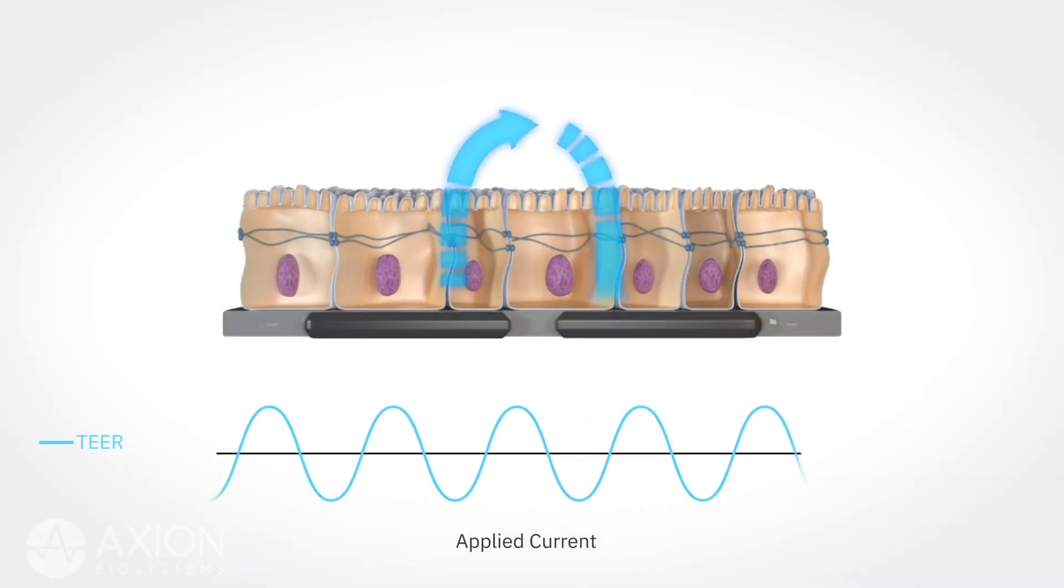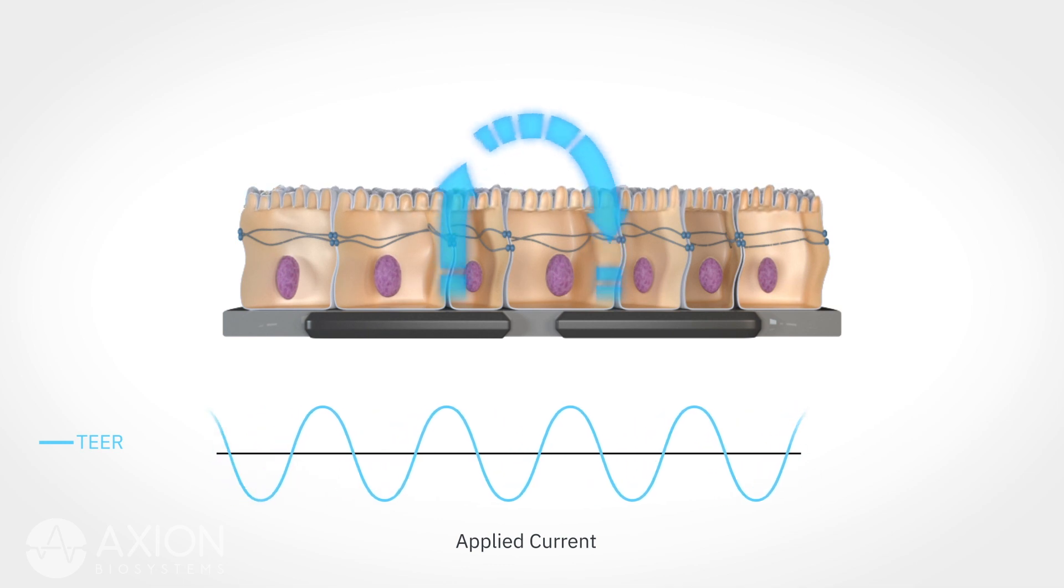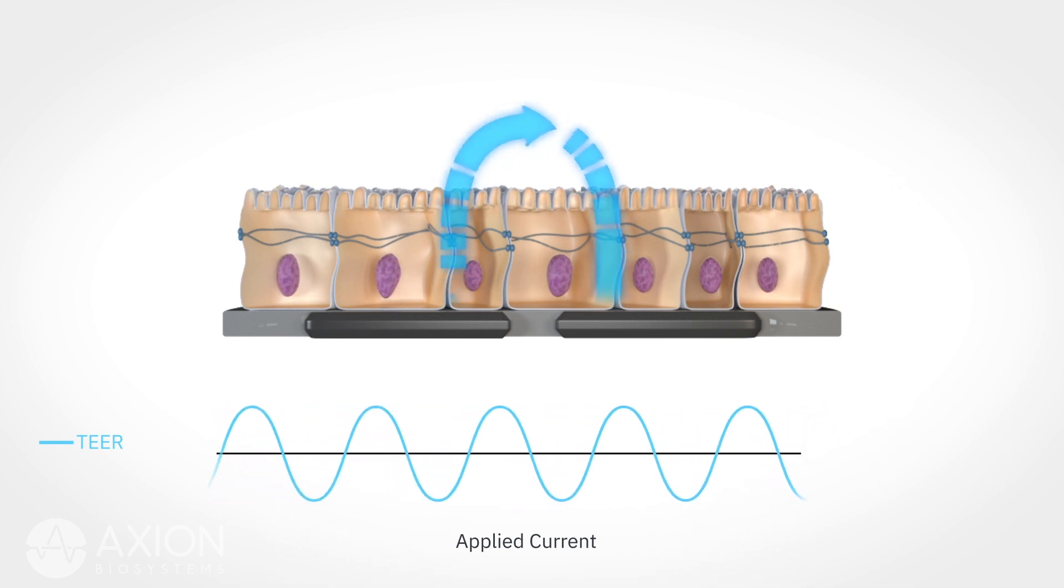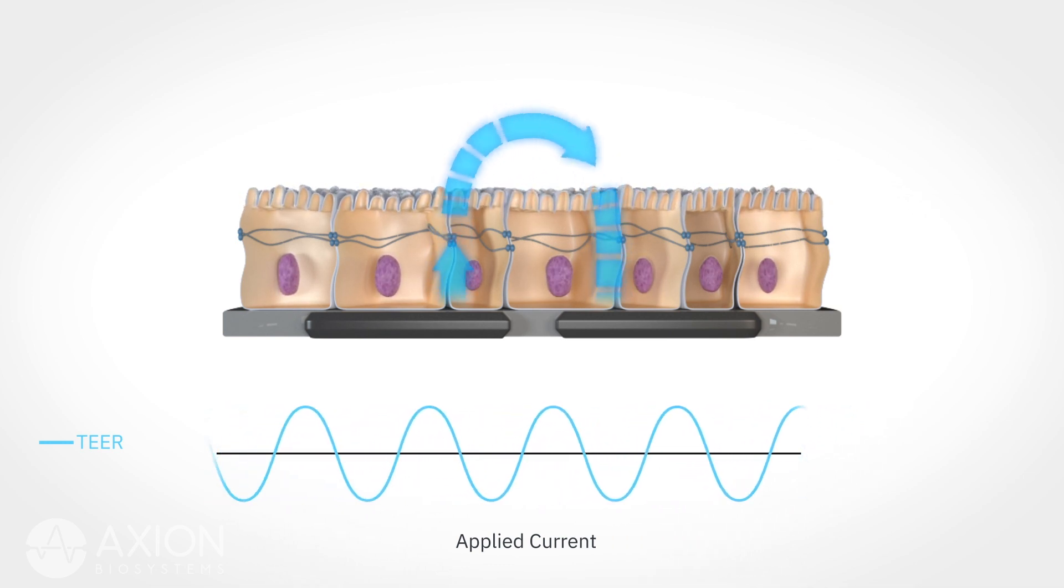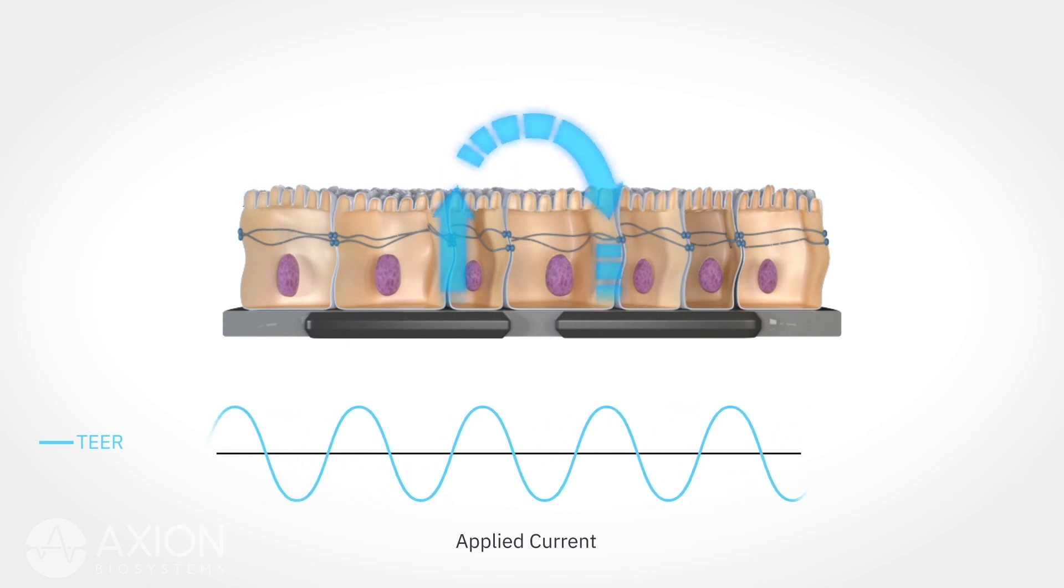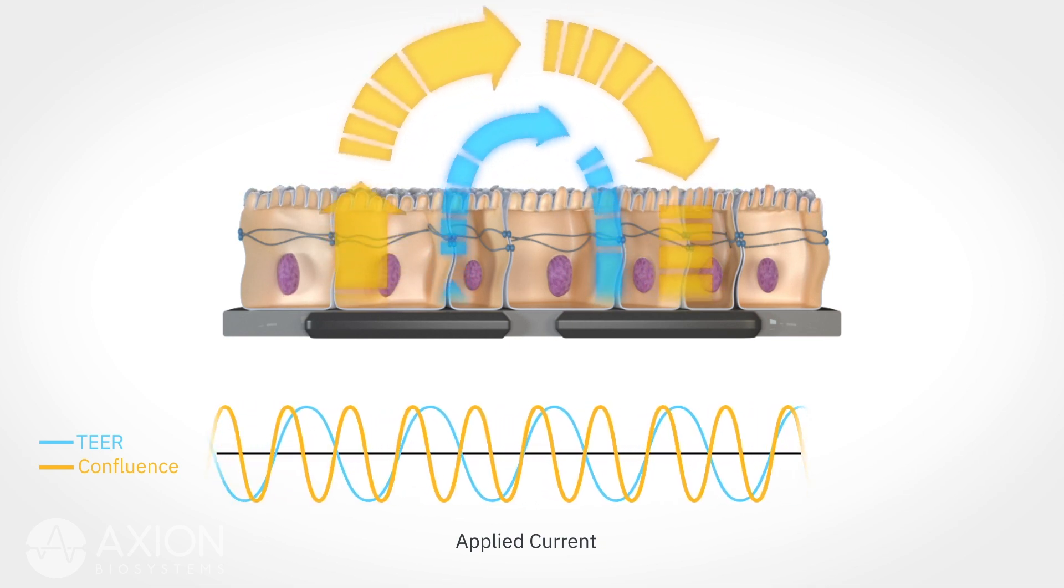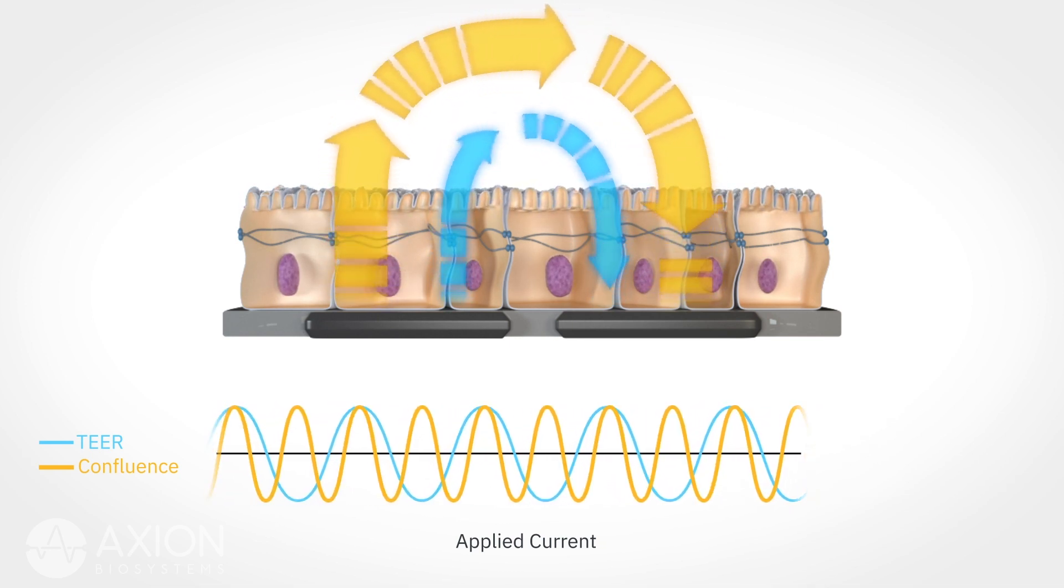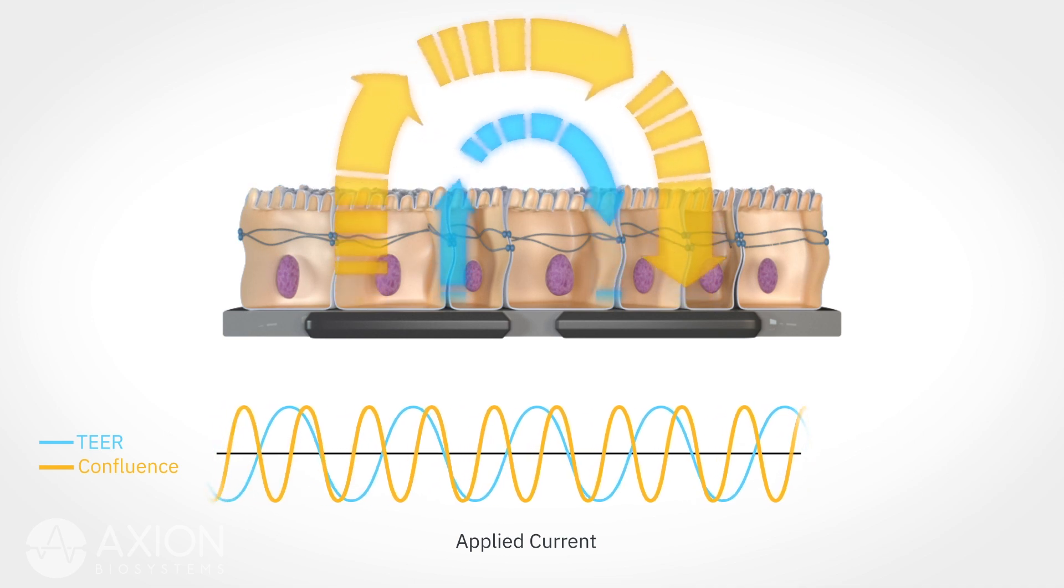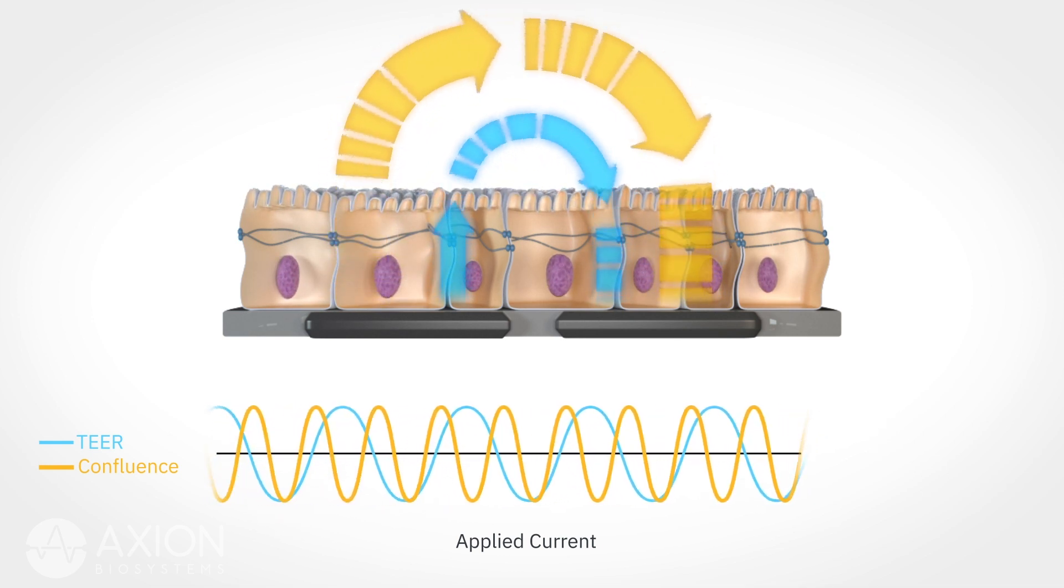By measuring at multiple frequencies, the Maestro-Z can simultaneously track TEER and confluence. Low-frequency measurements are sensitive to the barrier properties, while high-frequency measurements detect cell confluence over the well bottom. By measuring both, differences in confluence are controlled and accounted for in your analysis.